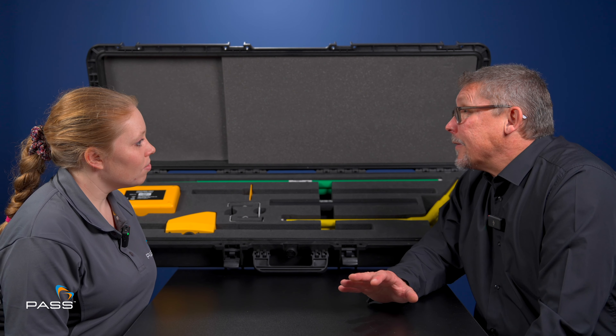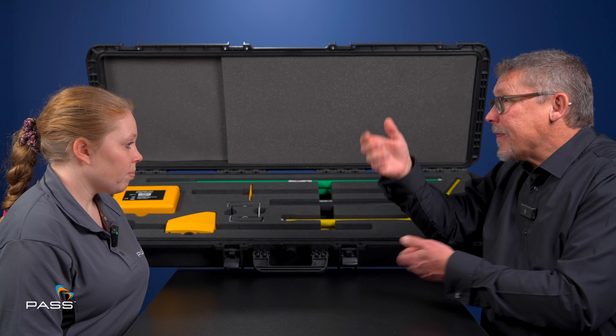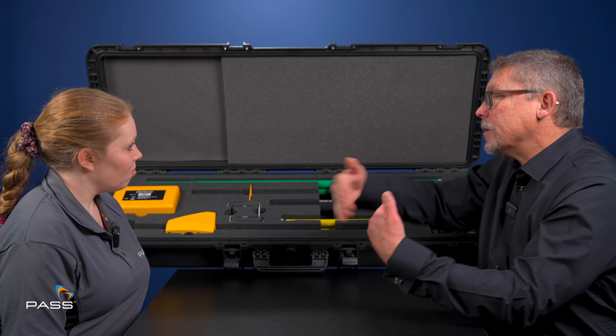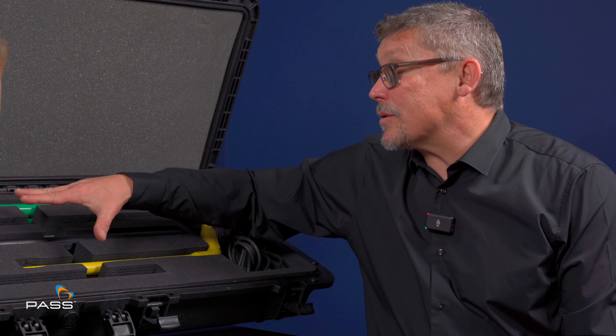I imagine that's very convenient because high voltage equipment isn't exactly accessible — that protects the public, but it can be annoying for engineers. Was that the thinking behind it? Yeah, absolutely. The whole thinking behind the original conception of these kits — we're dealing with Edgecombe, the original manufacturers, and they go right back. We've got examples in the office from the war. The kit that they used then was quite minimal — literally a high voltage detector with a dial and an extension pole. What's happened over the years is people have looked at it and said, would it be handy if we could check the phasing? So this is where the second rod came in. And then they said, oh, we need to be able to reach to it — so these extension poles came into it. What's happened over the period of the last 50 years or so, the kit has formed into, as you see it today, with every anticipated accessory that you need for high voltage testing solutions.